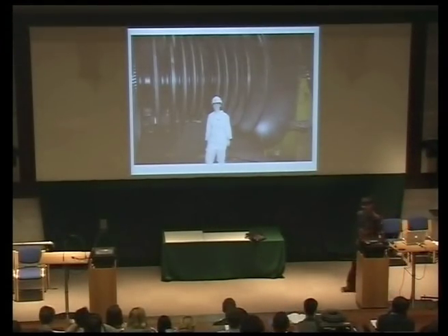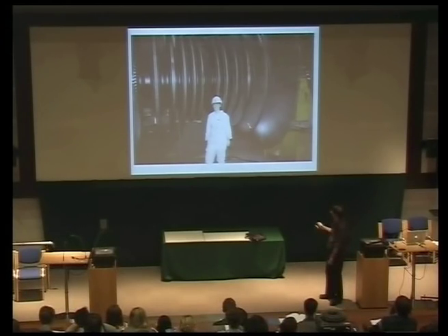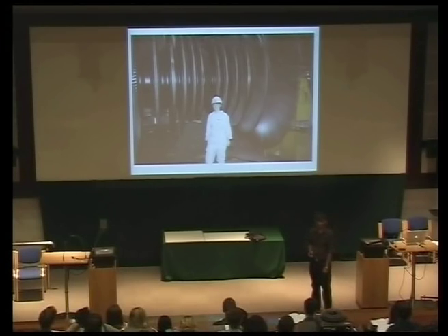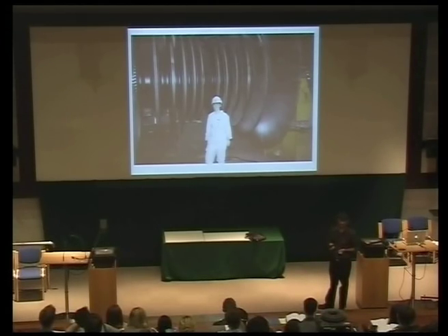I'm beginning now with power stations. And this is one of my former PhD students, Tracy Cool, who is about 1.7 meters high. Okay? And that is a steam turbine. So you can see the scale of the operation. This rotates at about 3,000 RPM for something like 30 years, sustaining steam temperatures of up to 600 degrees centigrade. So this is a very, very critical component.